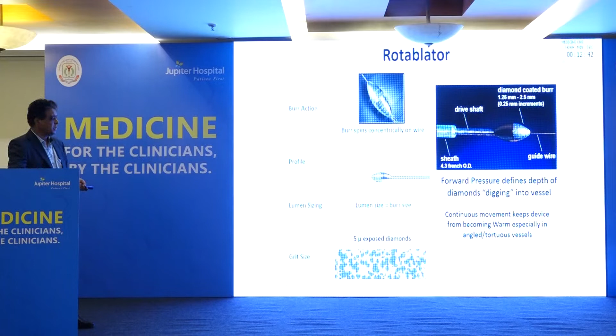Nowadays, we are using a handheld rotational angioplasty burr, where conventionally we used to require 2 operators. Now we are operating with a single operator. We have a foot pedal, Dynaglide. There are some special buttons we have to manage with the foot pedal, and certain buttons we have to manage with the hand, where 2 people are required, because we have 2 other channels to press. These are the fluoroscopic channel and the image acquisition channel. So 2 people are required to perform conventional angioplasty with a rotational angioplasty burr. Next.